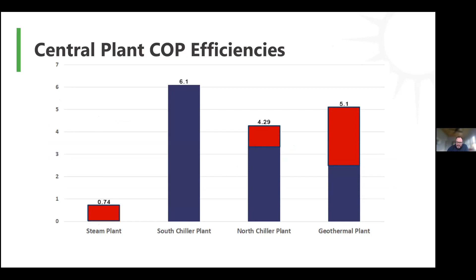That obviously helps drive energy reduction and cost reduction. It's interesting to note there are different plants throughout their campus. Their original steam plant was only at 0.74 from an efficiency perspective, whereas the south chiller plant, which has a lot of simultaneous load, and the geothermal plant are operating on an annualized basis north of 5 from a coefficient of performance perspective, which is exceptional.